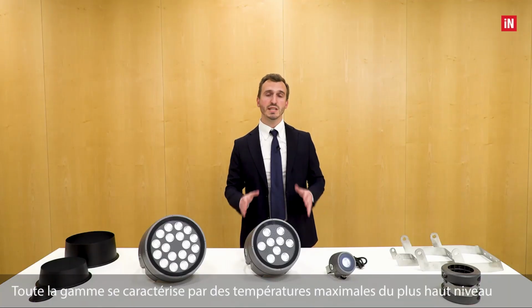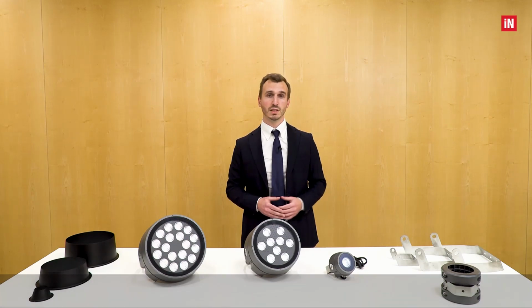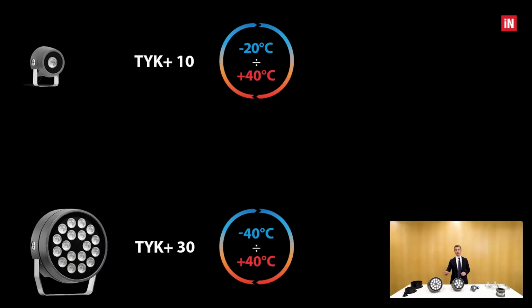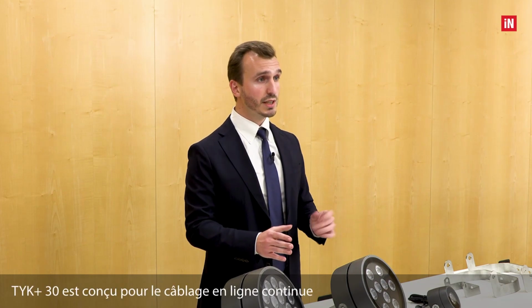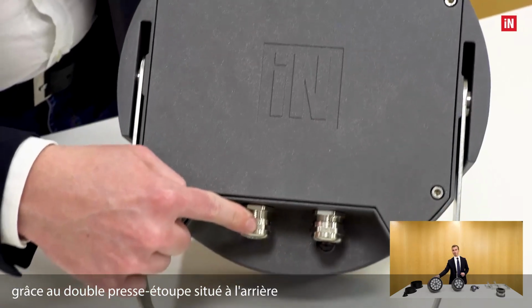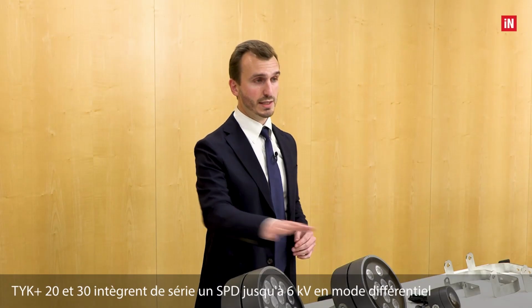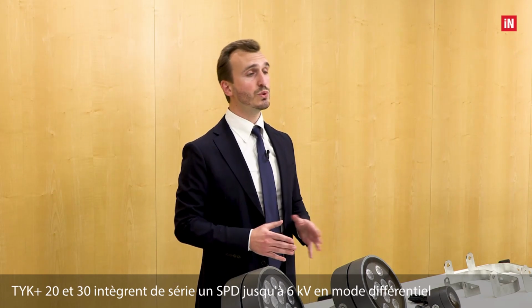The whole range is characterized by a maximum operating temperature of the highest level. The TYK Plus 10 and the TYK Plus 30 arrive up to plus 40 degrees Celsius, the TYK Plus 20 at an impressive plus 50 degrees Celsius. The TYK Plus 30 is designed for continuous line wiring thanks to the double cable gland on the back. The TYK Plus 20 and 30 integrate an SPD, a surge protection device, up to 6 kV in differential mode.